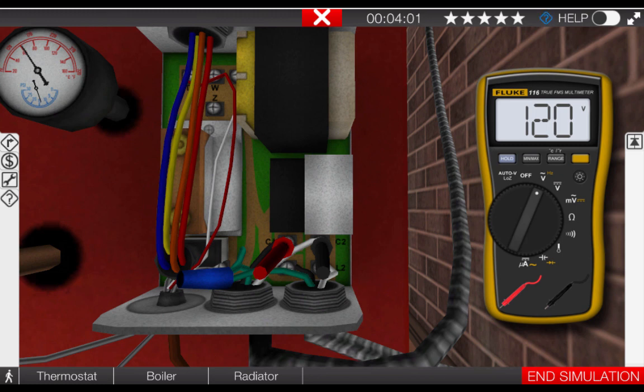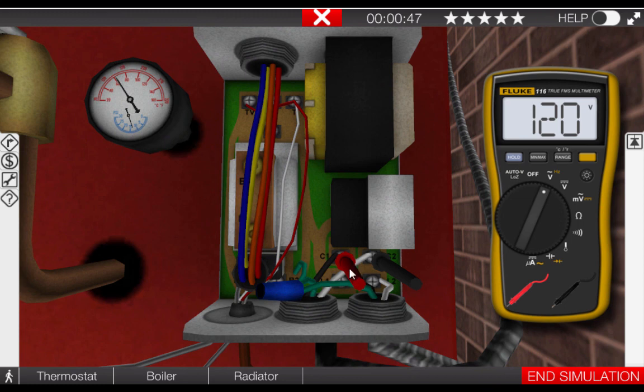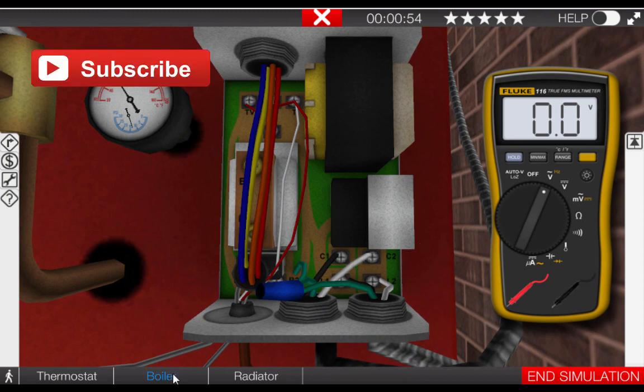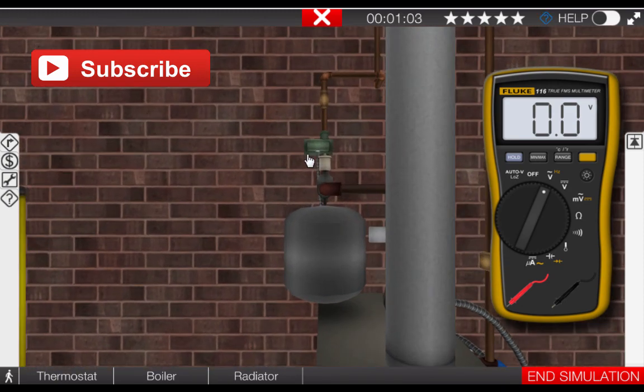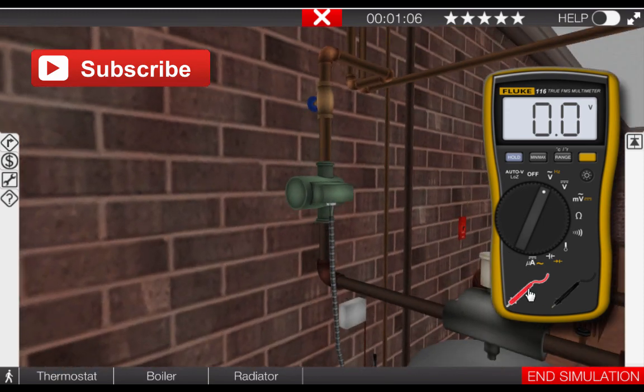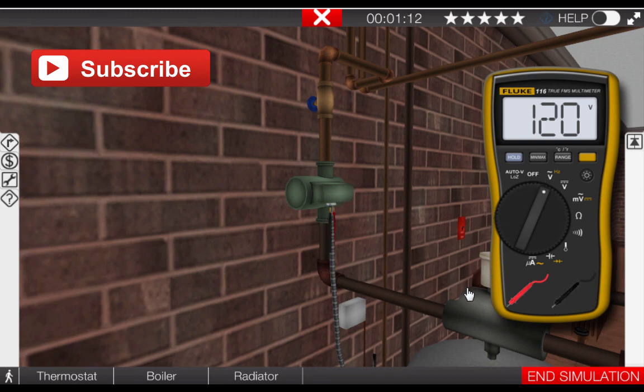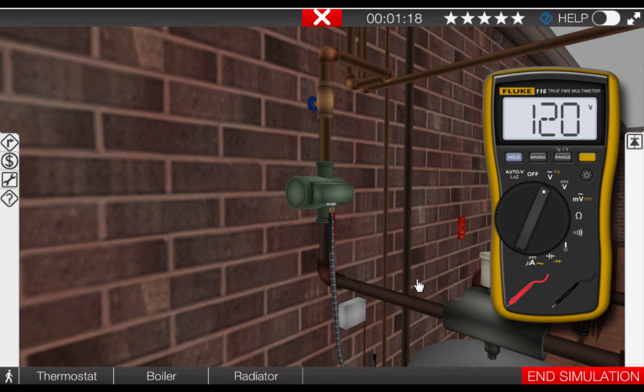To eliminate the possibility of a broken wire or faulty connection, let's measure for this 120 volts at the circulator pump itself. Remove the meter leads and store them back at the meter, and replace the cover of the combination aquastat. Right-click the circulator to center it in your field of view, zoom in, and place the meter leads at the glowing hotspots. Here we can see 120 volts at the circulator pump yet it is not running — this verifies the circulator pump is faulty and needs to be replaced.